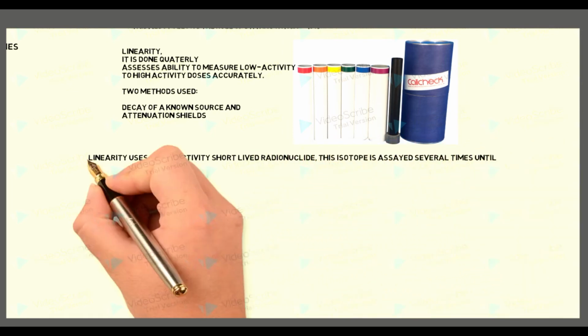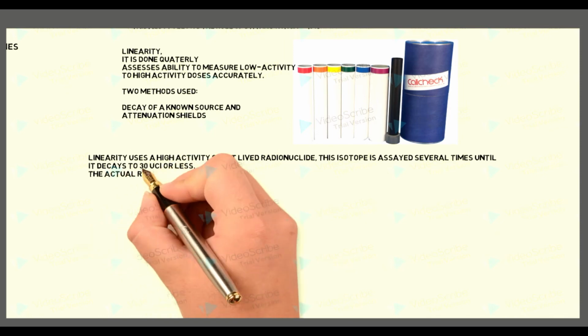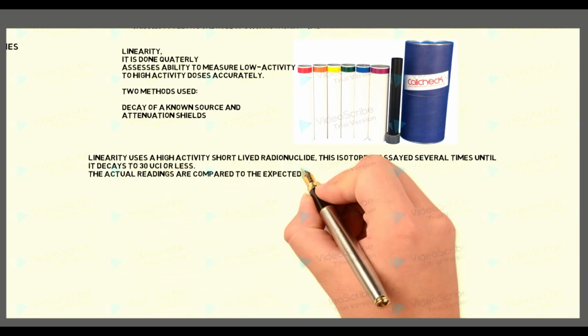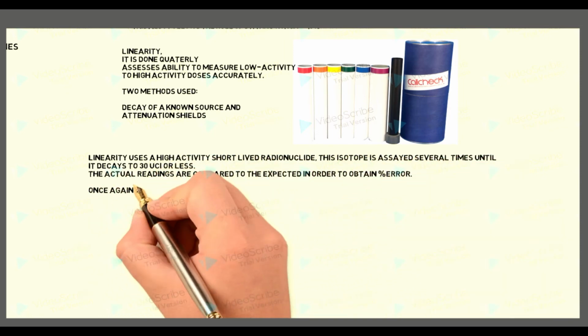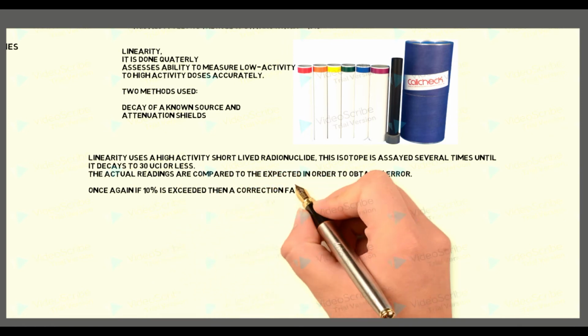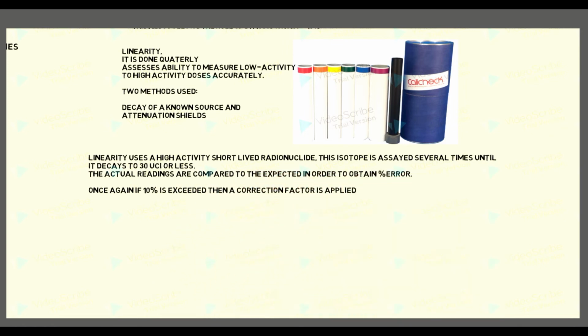This isotope is assayed several times until it decays to 30 microcuries or less. The actual readings are compared to the expected in order to obtain a % of error. Once again, this also follows the 10% window, and if more than 10%, a correction factor is applied.